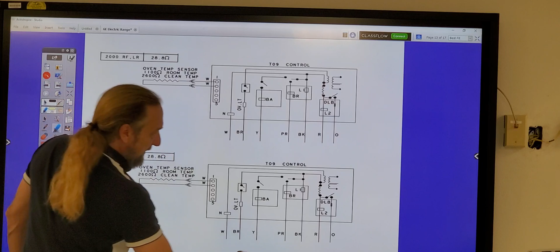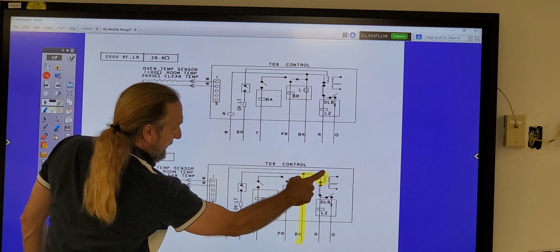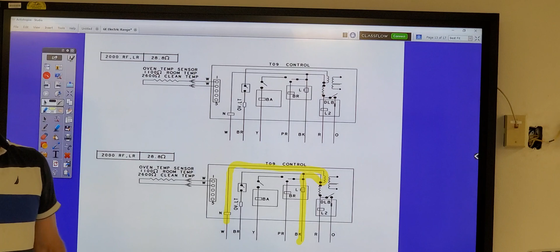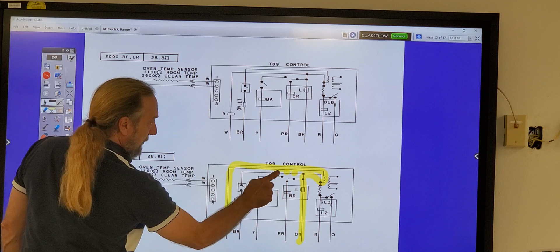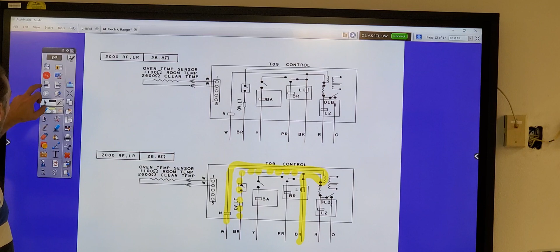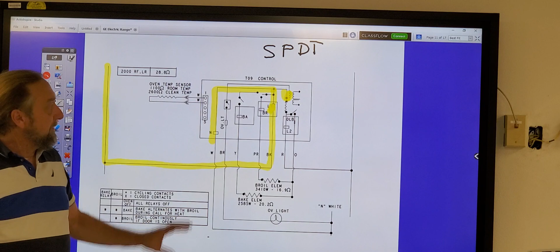Very good. So if we look, line 1, which is black, is coming in here and goes to the transformer and then comes out here, out the neutral. That's the way it should have been drawn. Now if you look here, they connected line 1 also to the light switch, and coming out here is the light switch. If we look at the full diagram, if this was line 1 coming to the light switch, it goes to the light bulb, and look, the light bulb ends at neutral. That would make sense. So this is an incorrect drawing.